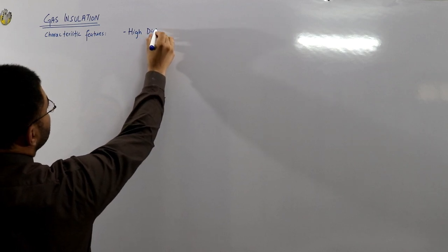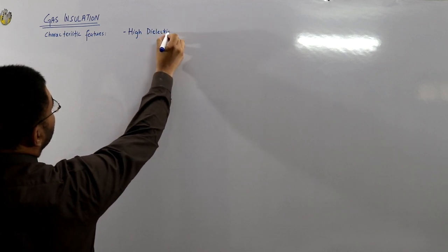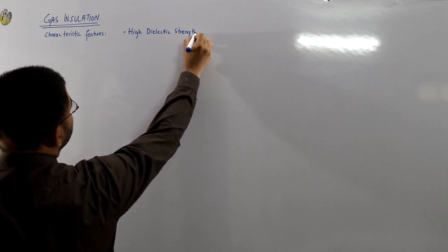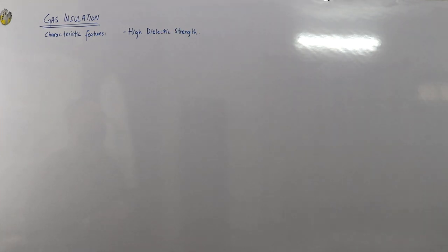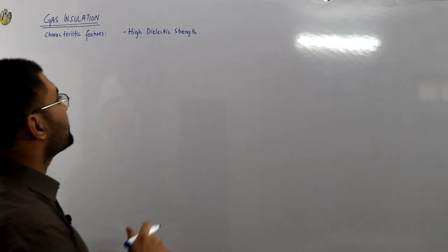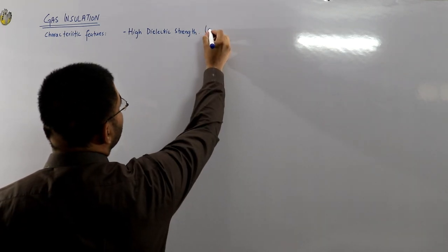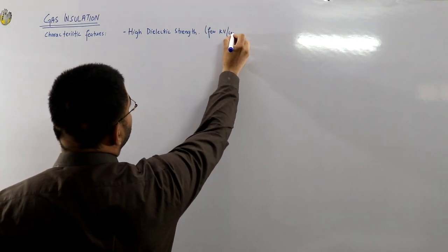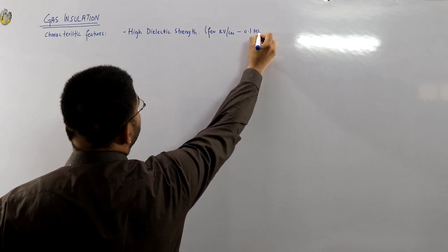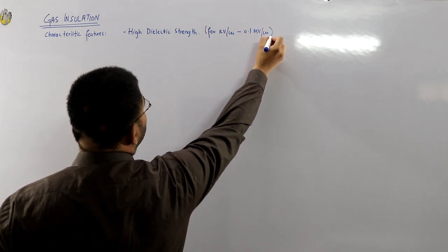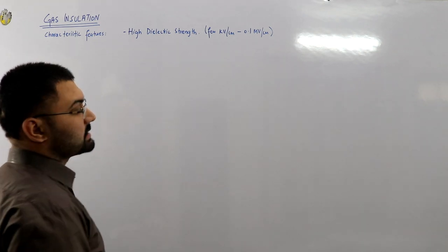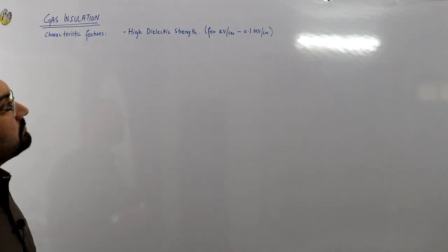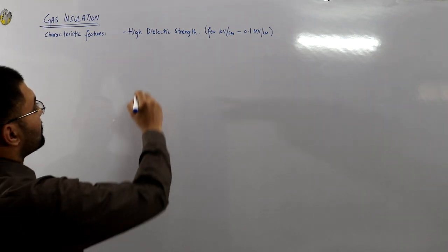Number one: it must have a high dielectric strength. We are using it for the purpose of insulation, so the higher the dielectric strength, the better the insulation. Gases roughly have a dielectric strength of a few kilovolts per centimeter up to a maximum of 0.1 megavolts per centimeter, which is 100 kilovolts per centimeter.